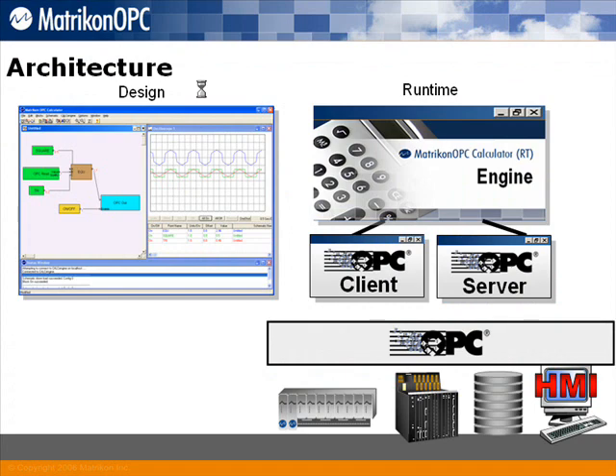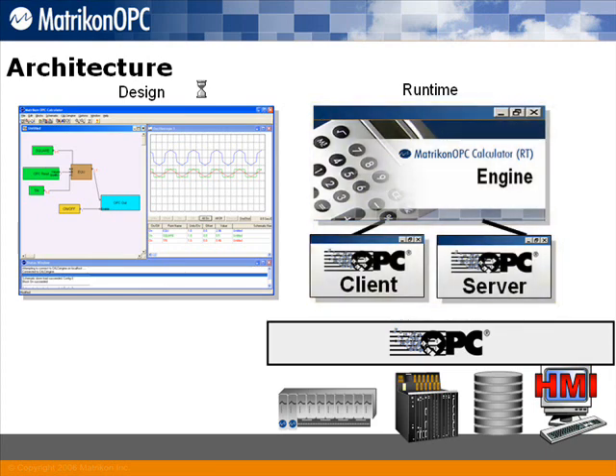Before we get going it's important to understand the components of the calculation package. There is a design environment and a runtime environment. The design environment is where you'll build, manipulate and edit your OPC calculations using the block editor. The runtime environment is where the calculations are actually executed. It has both an OPC client and an OPC server. The OPC client connects to external OPC servers to both read and write data. The OPC server presents the results of the calculations, or serves as a method for bringing data into the calculation package.